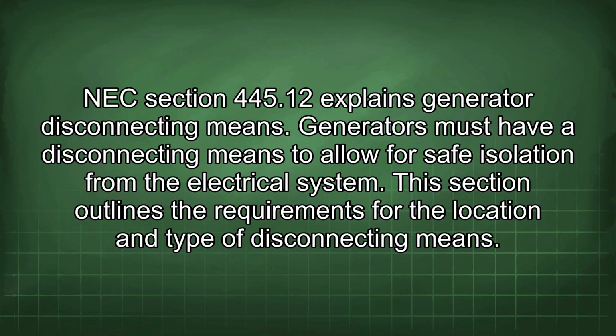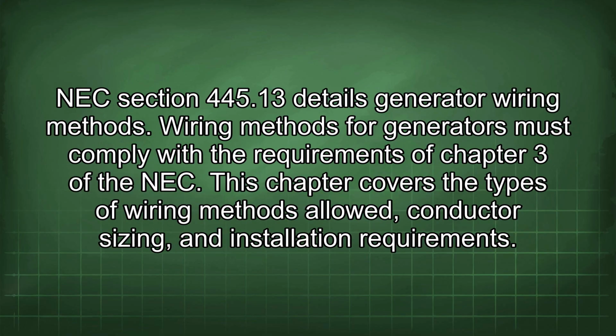NEC Section 445.12 explains generator disconnecting means. Generators must have a disconnecting means to allow for safe isolation from the electrical system. This section outlines the requirements for the location and type of disconnecting means. NEC Section 445.13 details generator wiring methods. Wiring methods for generators must comply with the requirements of Chapter 3 of the NEC. This chapter covers the types of wiring methods allowed, conductor sizing, and installation requirements.